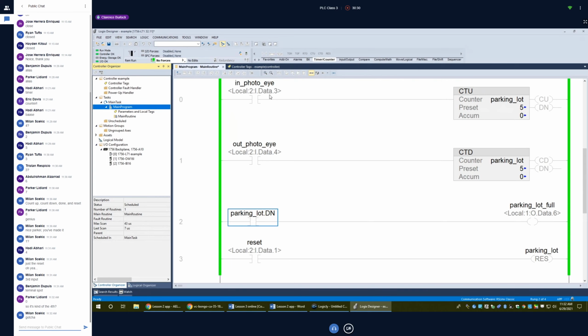So the idea there is if you have the input module, the door open, and you're going to terminate the wire, which terminal do you terminate it under? Well, you terminate it under the fourth terminal down, because terminal 1 would be input 0, terminal 2 would be input 1, and so on and so forth. What else we got here?